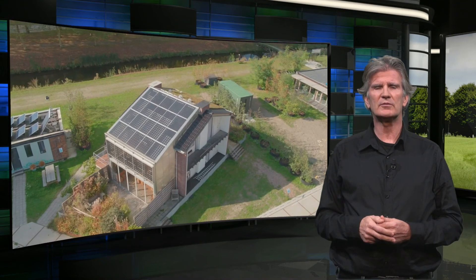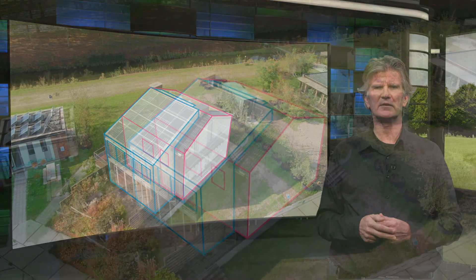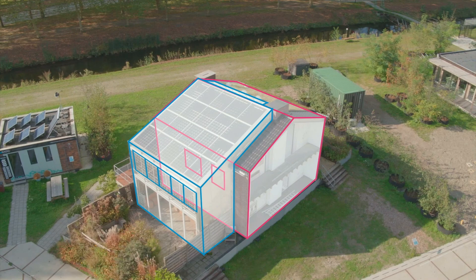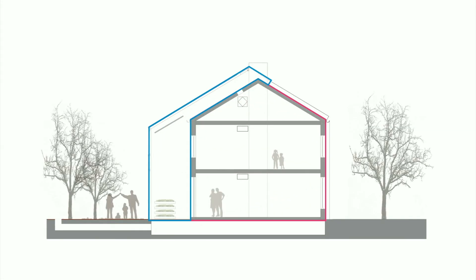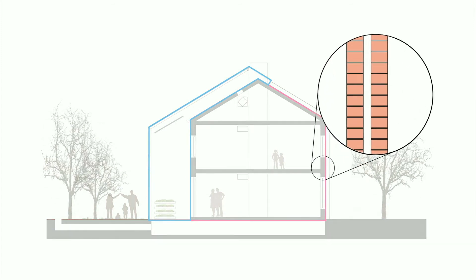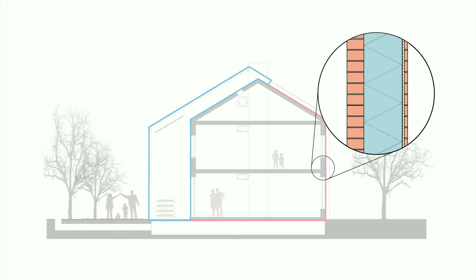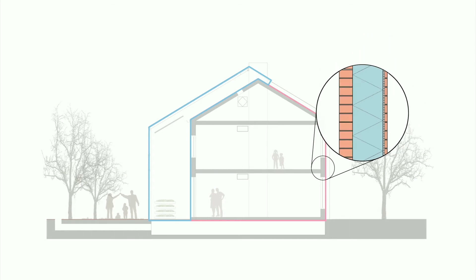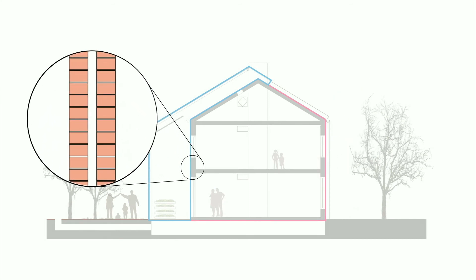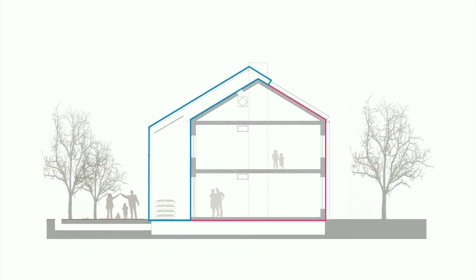Here we will show you how thermal insulation is applied in the Pret-de-Loger house. On the north facade, insulation is applied to the outside of the existing wall. The original outer masonry slab is removed, and a 200 mm thick insulation layer is applied, covered with thin brick tiles. On the south side, the cavity in the existing brick wall is injected with loose fill insulation material. This performs less than the exterior insulation on the north side, but the greenhouse on this side also helps to reduce the transmission losses.